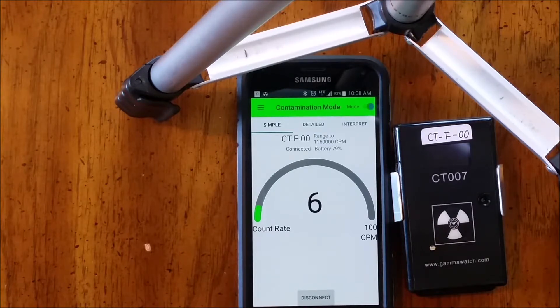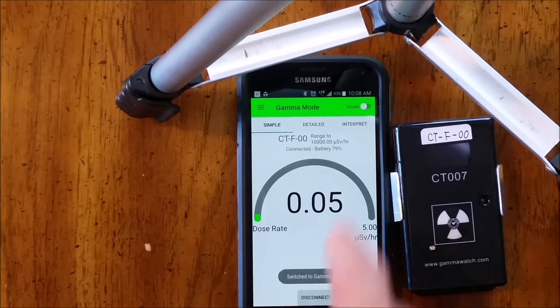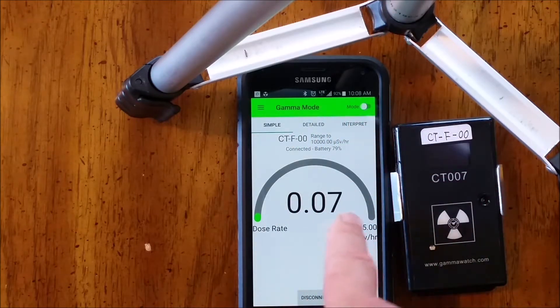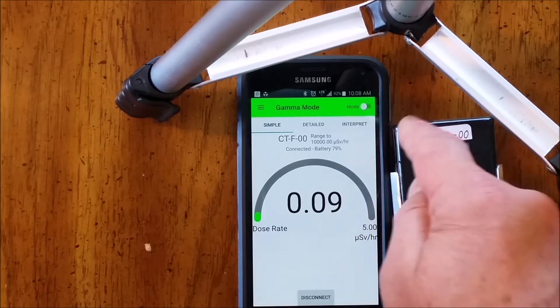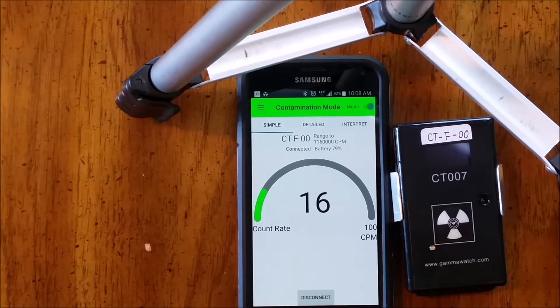And the app lets you switch between measuring contamination and measuring dose rate. So we're in dose rate gamma mode right now. And we switch back to contamination. That changes the units from CPMs to microsieverts an hour.